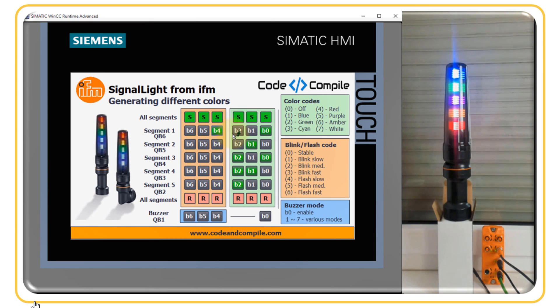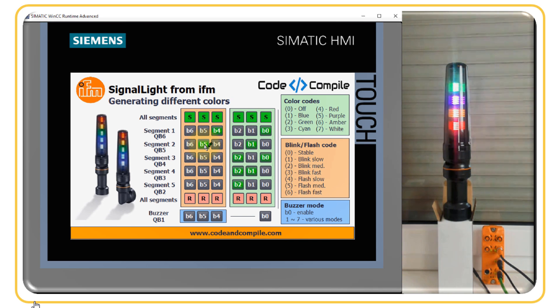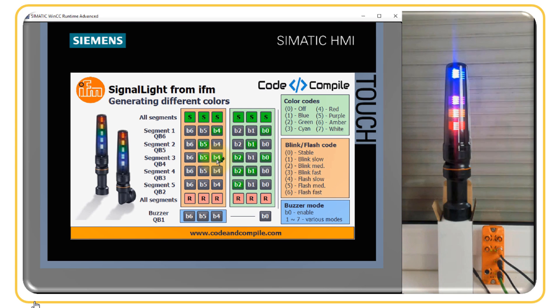To blink slowly, energize the first bit — segment one blinks slowly. For medium blinking, set value two (binary 10) on segment two — it blinks at medium frequency. For fast blinking, set value three on segment three — it blinks at higher frequency.